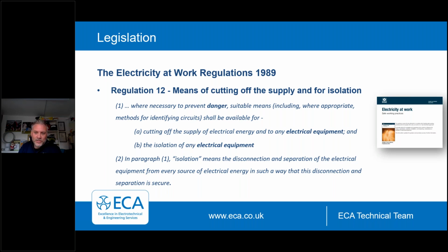We need to understand that isolation of electrical equipment prior to carrying out inspections or tests is not just a case of switching off the equipment. Isolation involves a procedure that must be followed before inspection or tests may be carried out. For equipment with a plug arrangement, isolation may be easily established - you can simply unplug it. But permanently connected electrical equipment, which is probably most of the equipment we deal with, will require more detailed consideration.